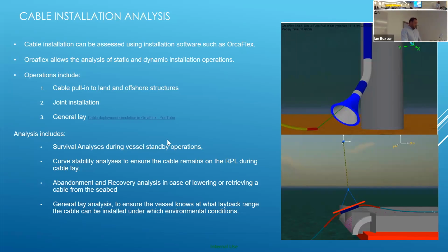So the first one I've got here, and I've got a video to demonstrate it, is the cable pull into land and offshore structures. The picture on your right here, imagine this is your substation. This is what's called a J-tube. Your offshore cable needs to be pulled into the substation, and then it's terminated into the switchgear on the substation, which then connects it to the array cables, which then connect you to the wind turbine generators.